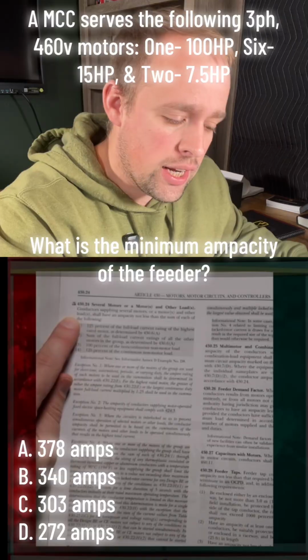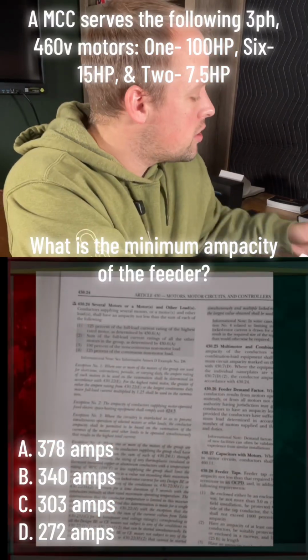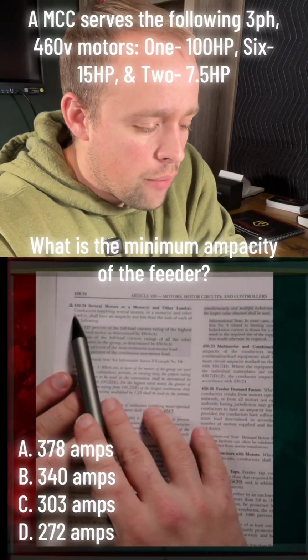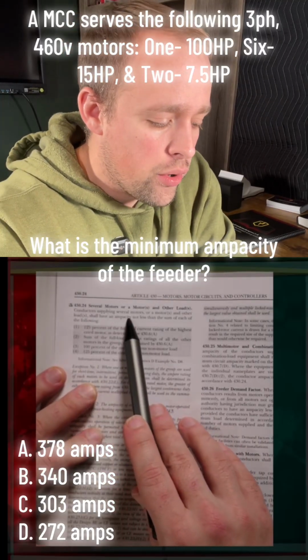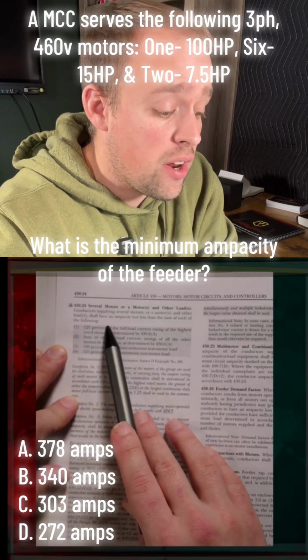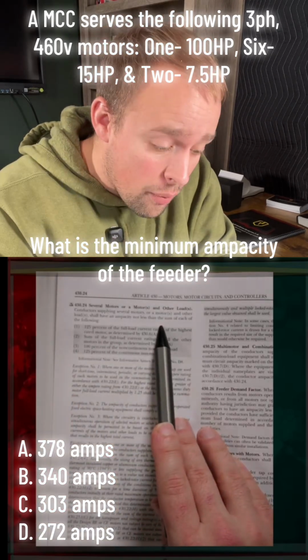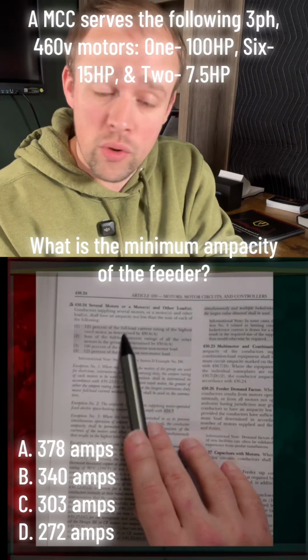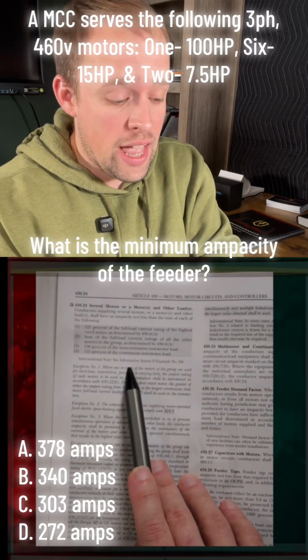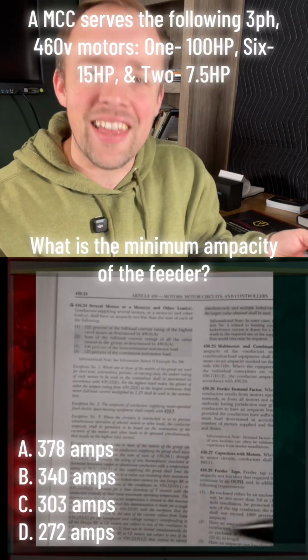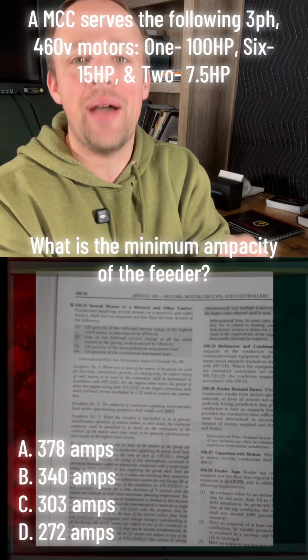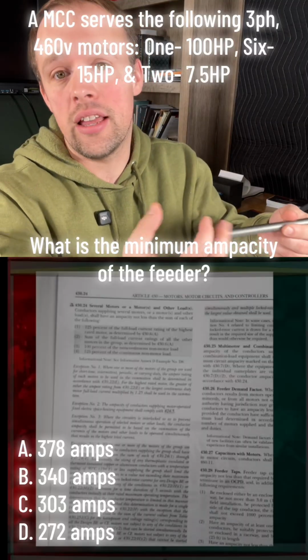Let's read it. It says conductors supplying, let's use my pen so you can follow along with me. Conductors supplying several motors or a motor and other loads shall have an ampacity not less than the sum of each of the following. So I'm going to read these 4, okay, and get ampacities for all 4 of these and then add them together. Based on that ampacity, I have to size and select my wire.